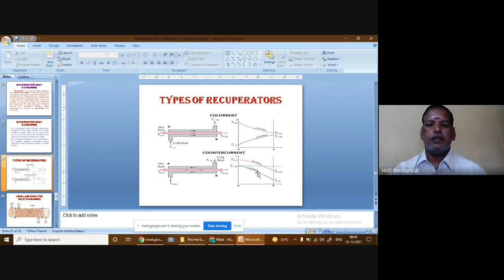But you can see that at the entry there is a large temperature difference between the cold fluid and the hot fluid, whereas at the exit the temperature difference will be very small. In the case of counter-current heat exchangers, both fluids are moving in opposite directions. In such cases, at the entry as well as the exit, and at all intermediate points, we maintain a nearly equal temperature difference, and thus the heat exchange will be better compared to that of the parallel flow heat exchanger. Hence, as I have told, counter-current heat exchangers are mainly used in waste heat recovery systems.